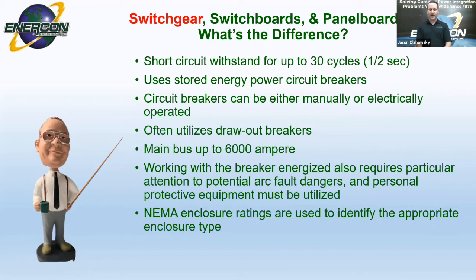NEMA ratings for environment, and these typically are ratings of NEMA 1 and NEMA 3R. NEMA 1 you would see mostly for just an enclosure, for switchgear or switchboards that are inside of a building. And then NEMA 3R, you would see that as an outdoor piece of equipment, protection for that.